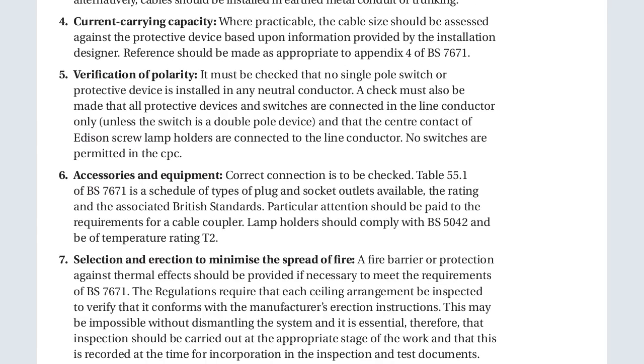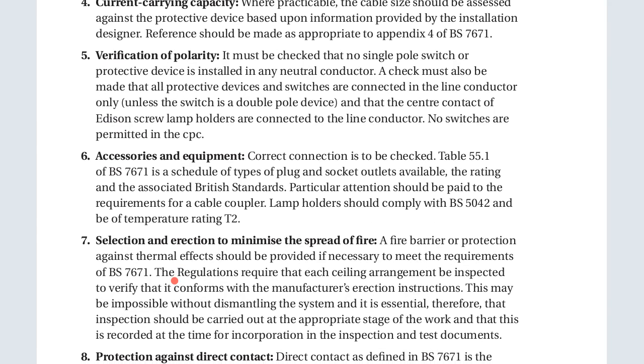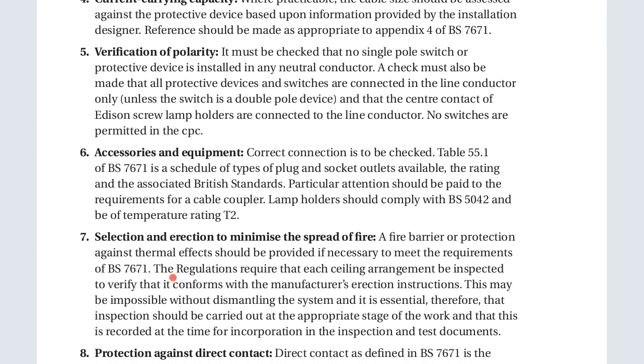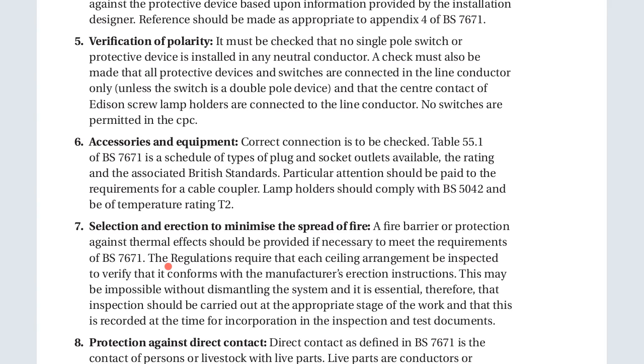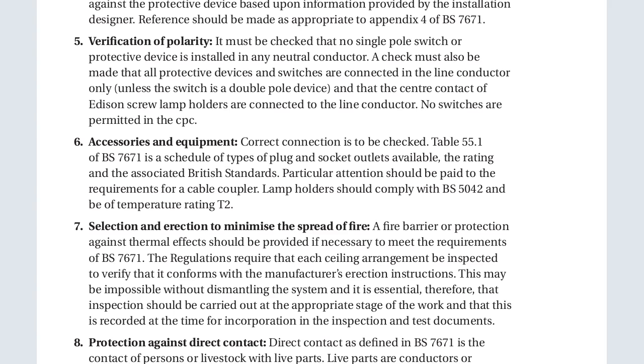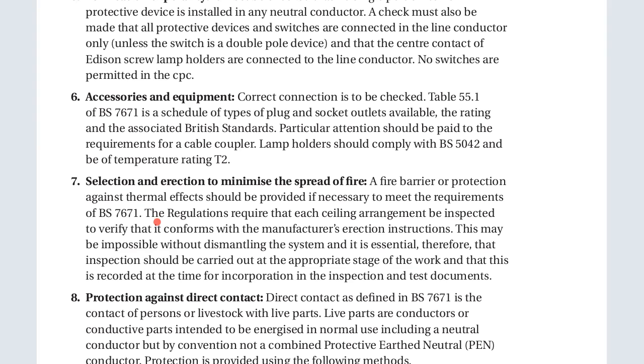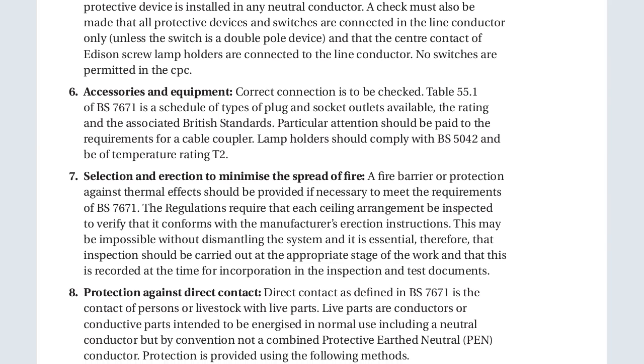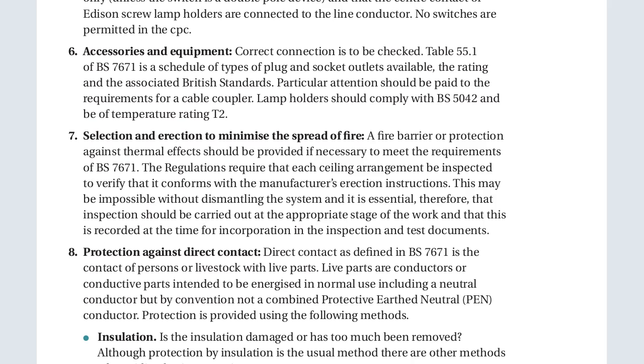Another one is the accessories and equipment. Correct connection is to be checked. That is, BS 7671 has a schedule of types of plug and socket outlets available, their ratings and the associated British Standards. Particular attention should be paid to the requirements of the cable coupler. The lamp holder should comply with BS 5042 and be of the appropriate temperature rating.